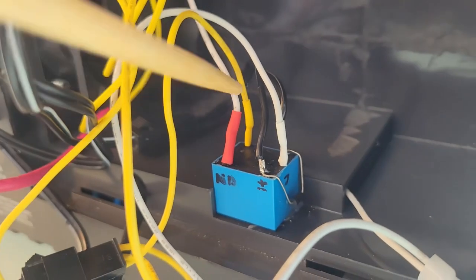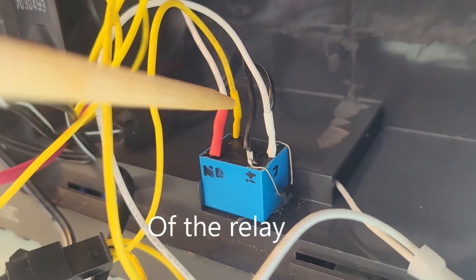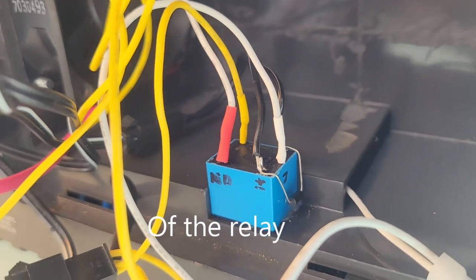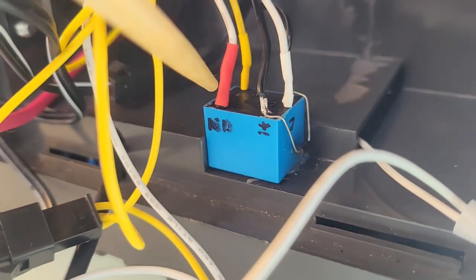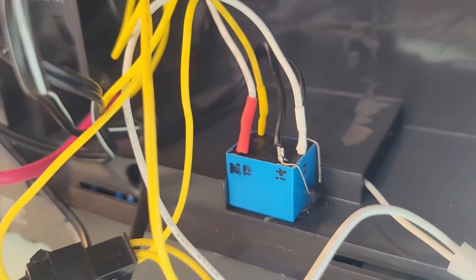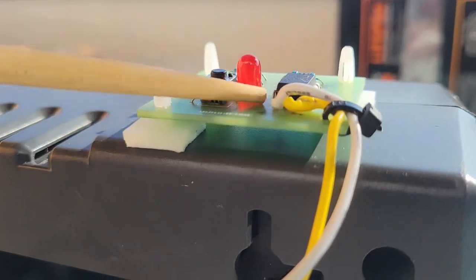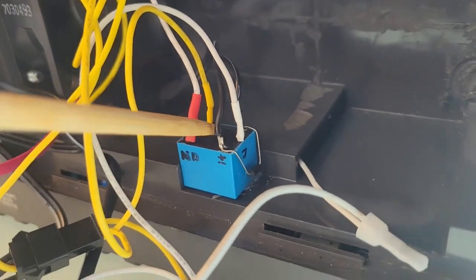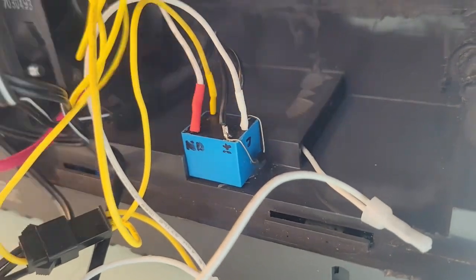Okay, so on the normally closed connection of the fan back there, the yellow one, we go to the fans. The normally open connection of the relay, we go to the power failure indicator. So we're using all 5 pins of the relay.